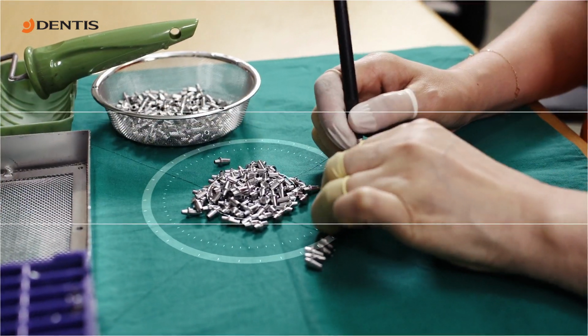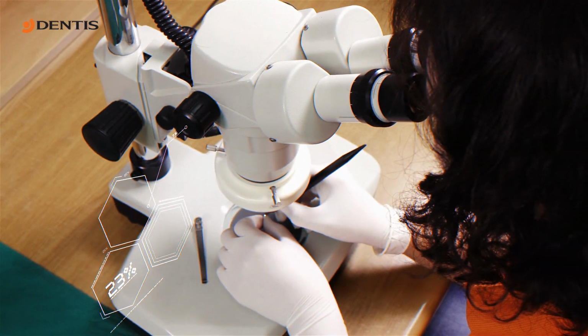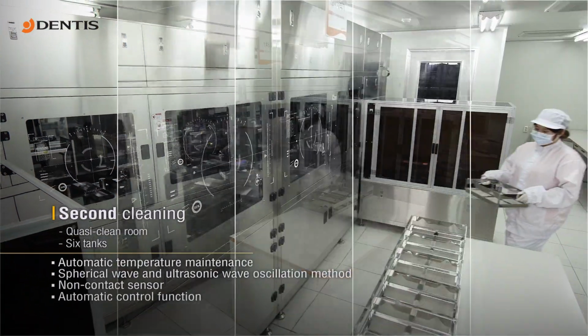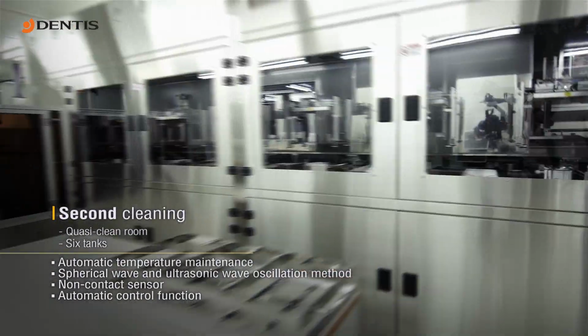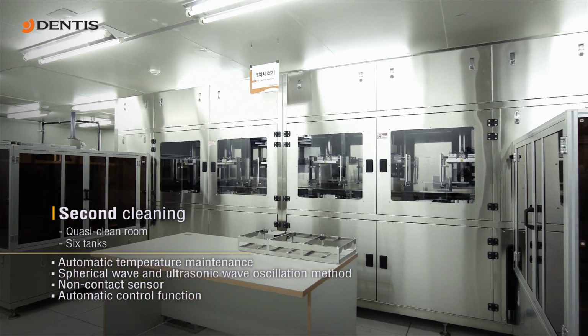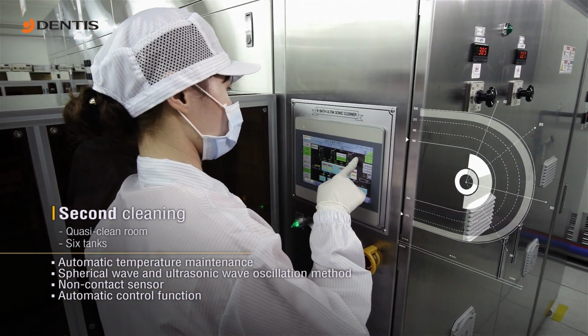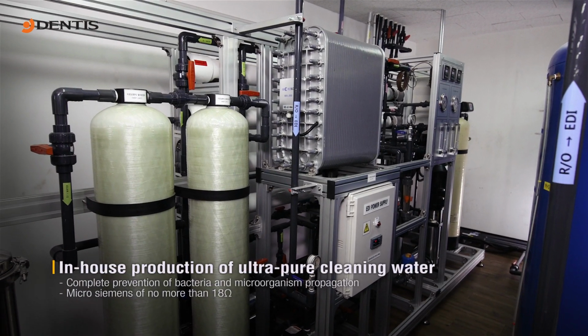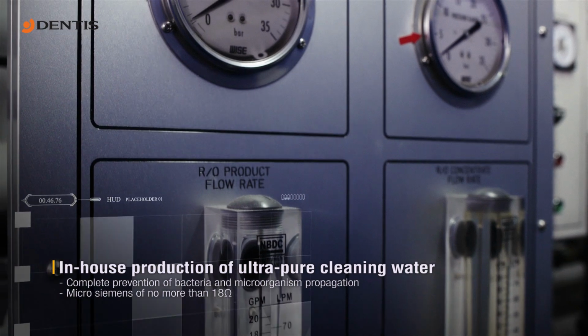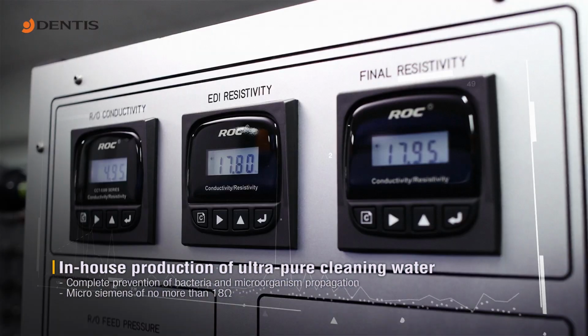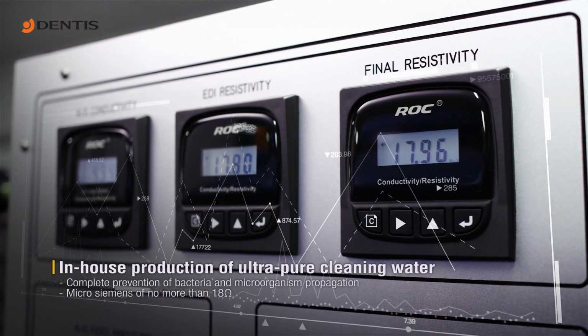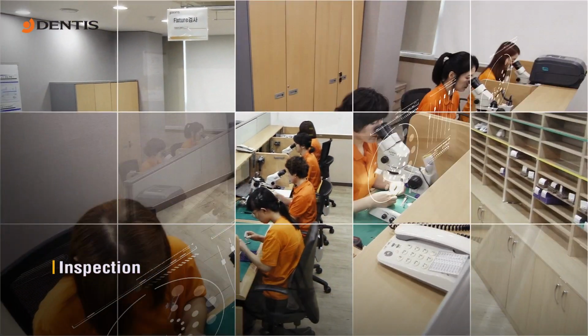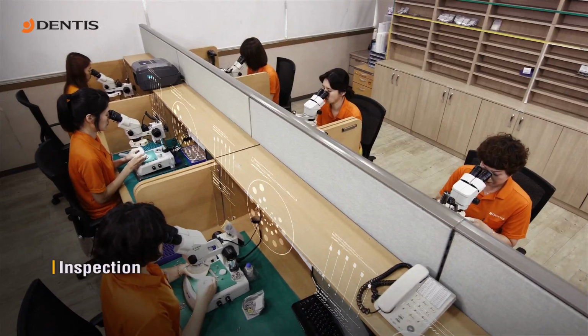And the deburring process is done to remove foreign substances and imperfections. In a quasi-clean room, the implants undergo ultra-precise cleaning in 6 tanks, as is done for such products as semiconductors. The DI water that is used at this stage is ultra-pure, 100% free of bacteria and microorganisms, and is produced in-house. The implants are inspected after the second cleaning.